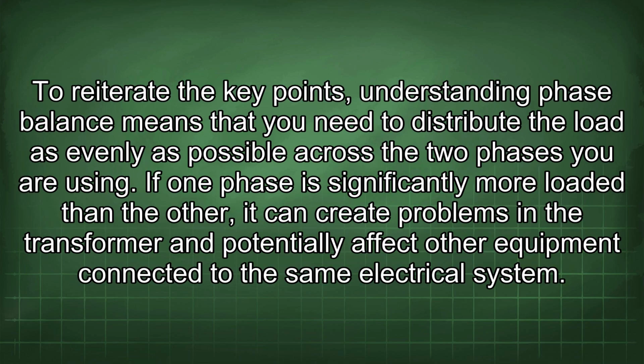To reiterate the key points, understanding phase balance means that you need to distribute the load as evenly as possible across the two phases you are using. If one phase is significantly more loaded than the other, it can create problems in the transformer and potentially affect other equipment connected to the same electrical system.